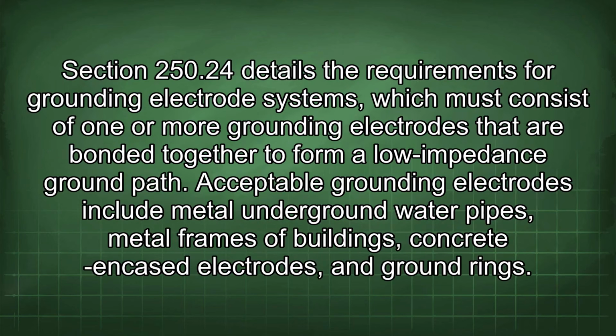Section 250.24 details the requirements for grounding electrode systems, which must consist of one or more grounding electrodes that are bonded together to form a low-impedance ground path. Acceptable grounding electrodes include metal underground water pipes, metal frames of buildings, concrete encased electrodes, and ground rings.